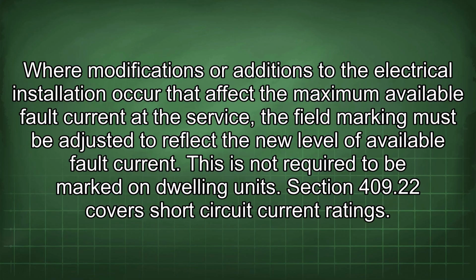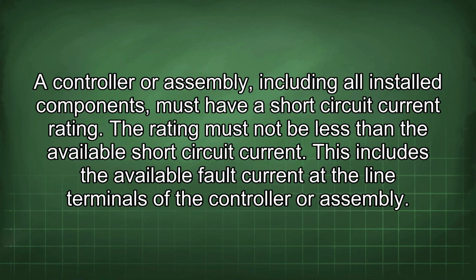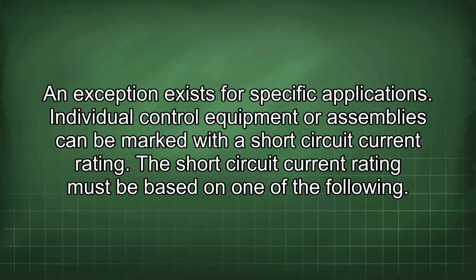Section 409.22 covers short-circuit current ratings. A controller or assembly, including all installed components, must have a short-circuit current rating. The rating must not be less than the available short-circuit current. This includes the available fault current at the line terminals of the controller or assembly. An exception exists for specific applications. Individual control equipment or assemblies can be marked with a short-circuit current rating. The short-circuit current rating must be based on one of the following.